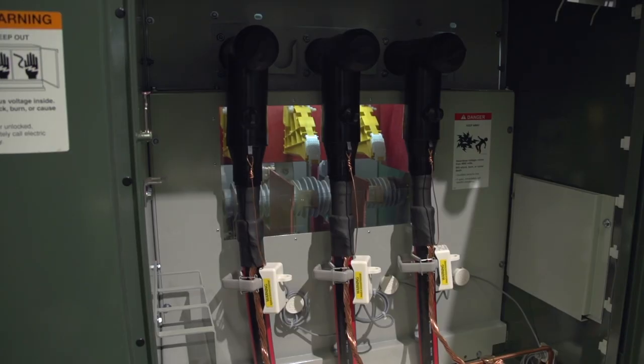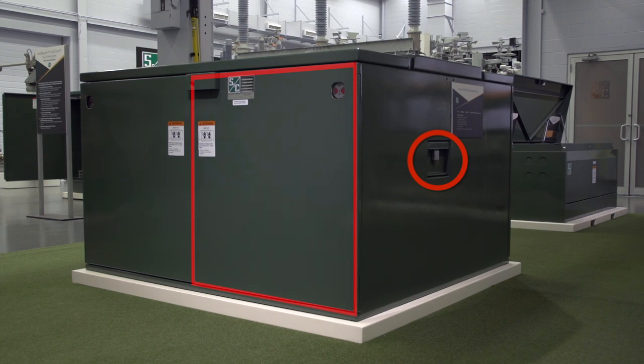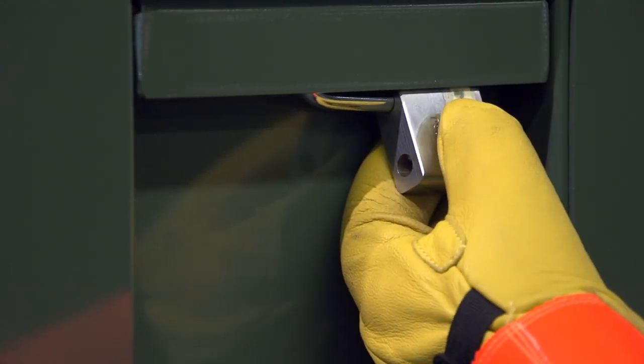The mini-rupter switch is a three-pole, 600-amp switch used to switch between power sources and can be operated outside the enclosure. The operating shaft, used to control the switch, is located on the same side of the enclosure with respect to the switch location. To open or close the switch, remove the padlock and open the switch operating shaft access cover.